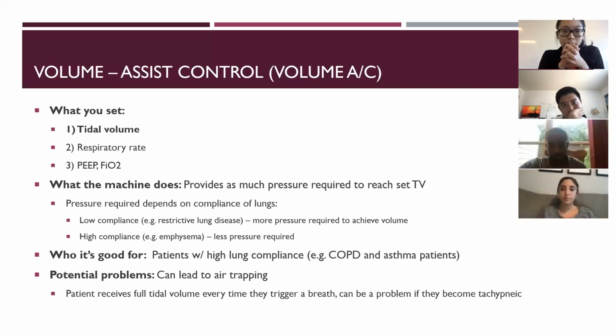The thing with volume assist control is that every time a patient tries to take a breath or every time the machine delivers a breath, they get the full tidal volume. So if I say I want 0.59 liters of air into this human, they are going to get that entire 0.59 every time the machine decides that it's appropriate to do so. So for example, if your patient becomes tachypneic and starts triggering a ton of breaths without really properly inhaling and exhaling, your machine is just going to keep shoving that 0.59 liters with every trigger. So this can obviously lead to air trapping. It's not good for the patient's physiology or their breathing. So this is a potential downside.